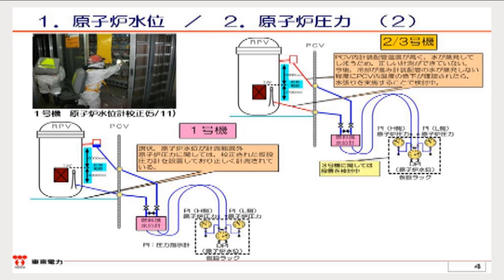Regarding the situation of each unit, as for Unit 1 at present, we finished the calibration of the water level gauge on May 11th, and the condensate pot of this water level gauge, named the L side, is filled with water. Regarding the water level in the reactor at present, it is undergoing downscaling, so we assume that the water level in the reactor of Unit 1 will be more than 5 meters below the core support plate. Now we are injecting water at the rate of approximately 4 cubic meters per hour. However, we estimate that water is leaking from the damaged part of the pressure vessel.